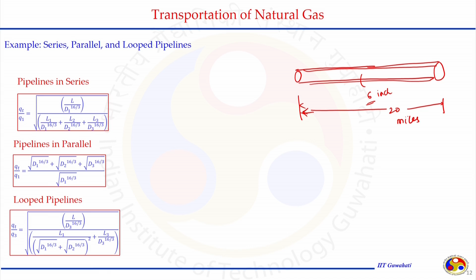Now, this pipeline is under consideration. We are not going to put in other details like gamma, z, or the relative roughness, because those do not appear when we are calculating the increase in gas capacity of the pipeline while installing a series, parallel or loop pipeline system. So, let us say a pipeline of 20 miles with diameter 6 inches is subjected to series, parallel and loop systems. We need to know the pressure at this end P1 and at this end P2, and here we are assuming P1 and P2 are a little far from both the compressor and delivery point. This is the segment which is not affected by the compressor or delivery point. It is just a segment of the long pipeline which we counted as 20 miles in length and 6 inches in diameter.